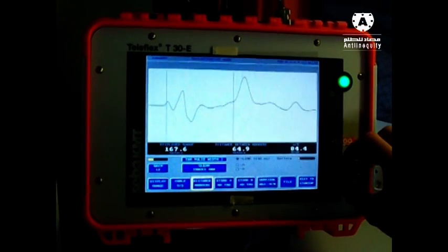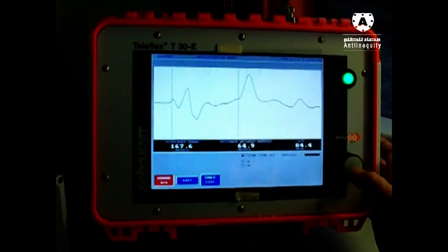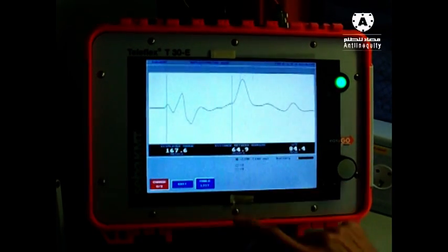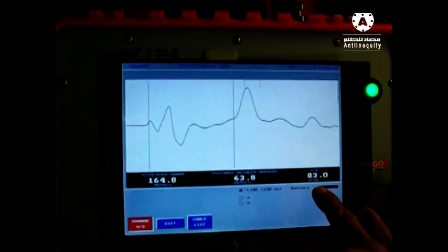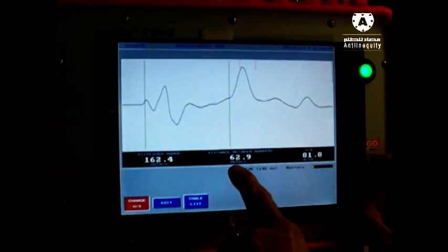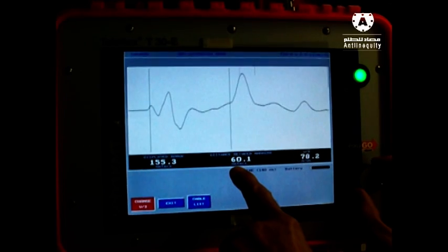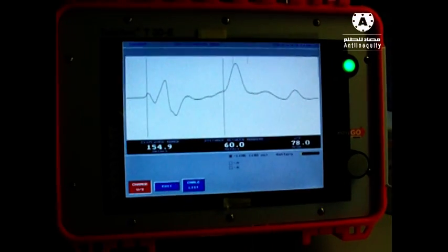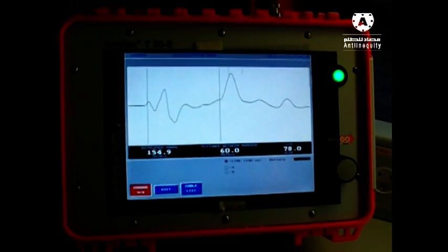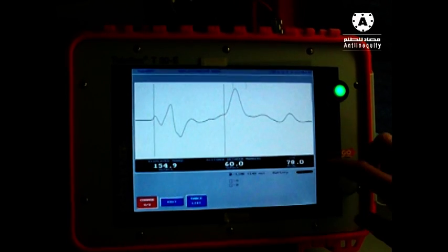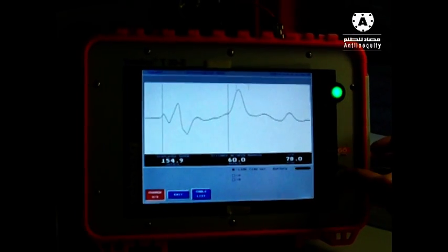Let's go back. We adjust now the velocity by hand. If our real length is only 60 meters, you see we have to decrease here the velocity so that we reach the real cable length at this point. That means the real cable length of our test span is in this special case 60 meters. If your cable is much longer than 60 meters, about 80 meters, you must do the same steps, but then you have to increase to reach the real value.